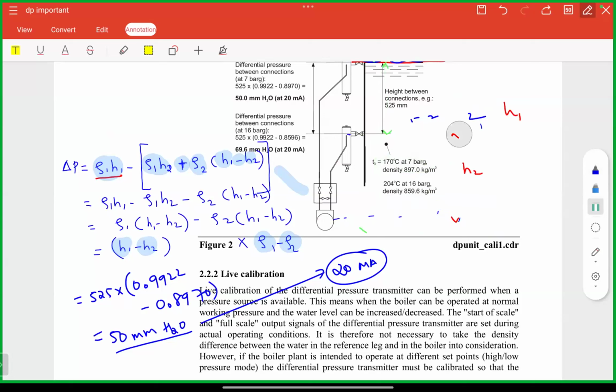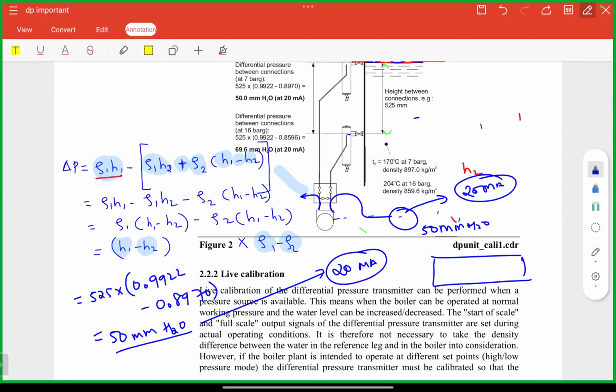This is your mathematical calculation. You are going to keep one end of the DP transmitter open, connect your pressure calibrator on the other end and apply the pressure of 50.0 mm of water column. It should generate 20 milliamp signal. If it does not generate 20 milliamp signal, span calibration is there. Yes, there will be two knobs, one for zero setting and one for span setting. Adjust the span setting so that corresponding to 50 mm of water column, the DP transmitter will produce the equivalent signal of 20 milliamp.